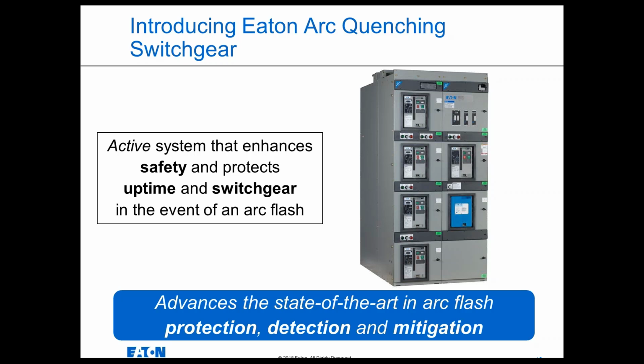It's an active system that enhances safety, it protects uptime, and it protects the switchgear in the event of an arc flash. And when I say it's an active system, I mean it's an intelligent system. It's relay-based. It's not passive. Traditional arc-resistant equipment is essentially a robust enclosure that just sits there. There's no intelligence to it at all. It just sits there passively, and if it's all buttoned up, all the doors are closed, it works as designed. Arc Quenching Switchgear is an active and intelligent relay-based system, and it really has advanced the state of the art for arc flash protection, detection, and mitigation.